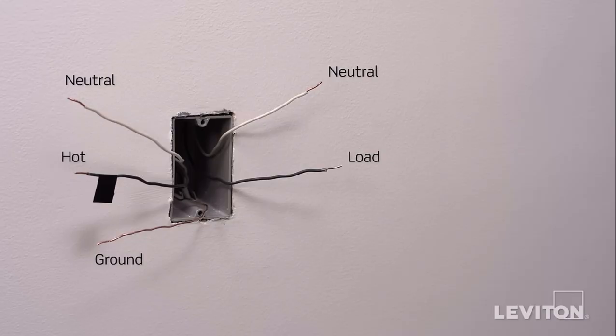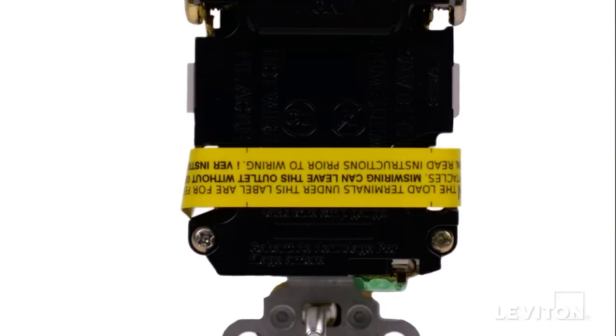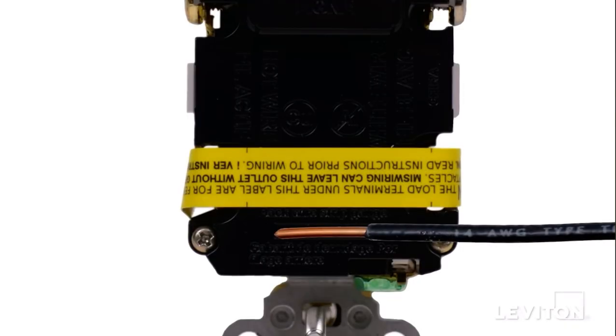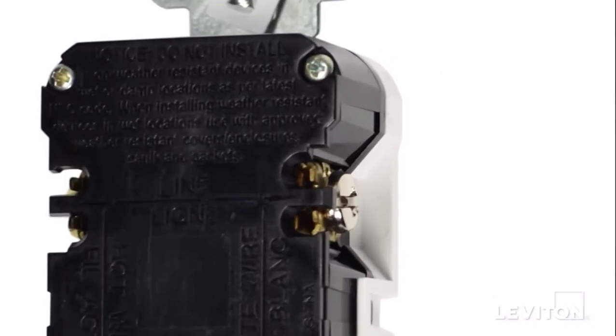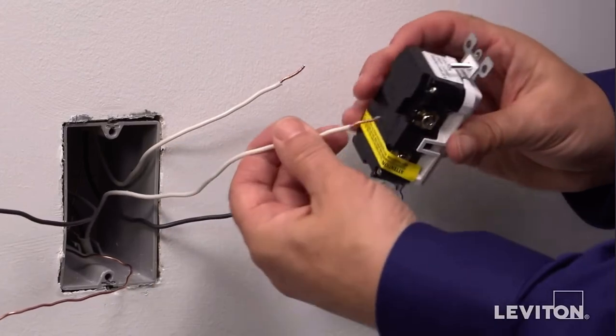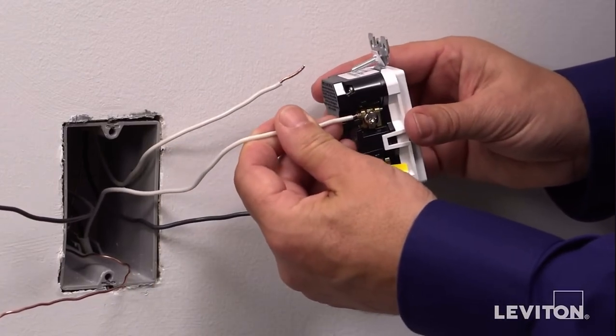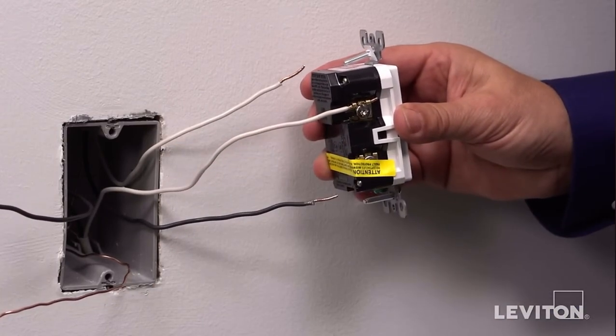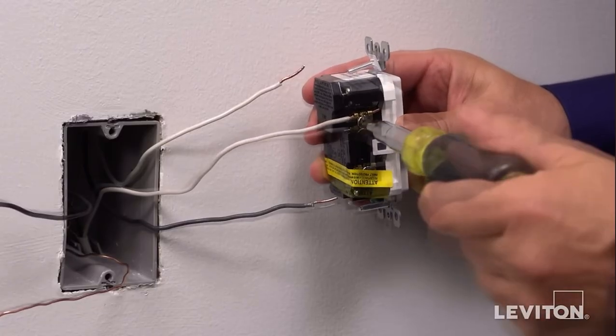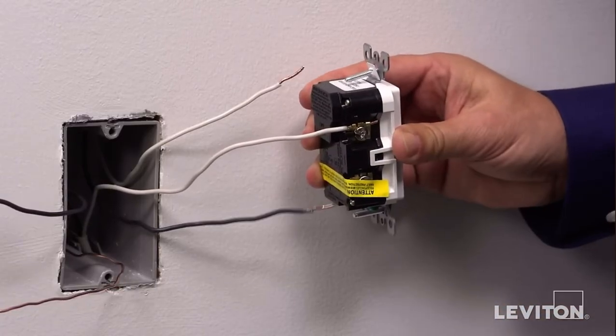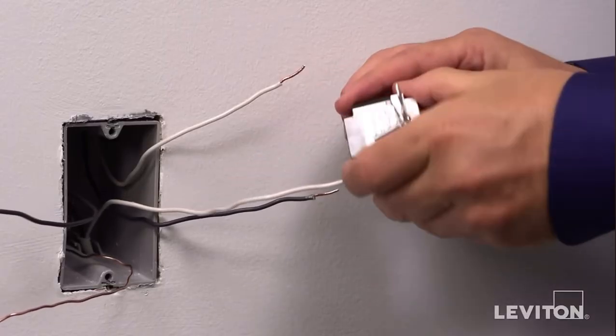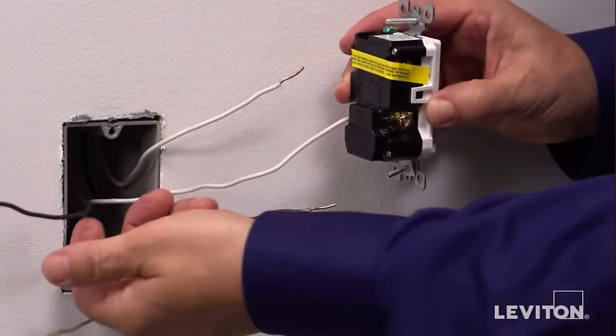Next, you need to be sure that the wires are prepared for installation. Start by making sure the wires are straight and stripped according to the strip gauge located on the back of the device. We will now wire the device. There are guide channels to help keep the wire in place. Begin with the line wires to the line terminals. The line terminals are those without the yellow sticker. The white line wire connects to the silver terminal, and the black line wire connects to the hot brass terminal.